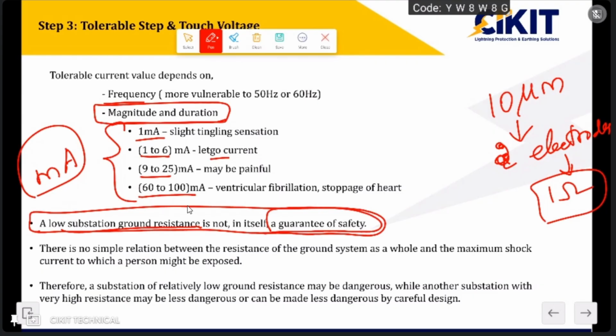They have also mentioned that there is no direct relationship between the safety and the ground resistance value. Even if the ground resistance value is higher, the design will be considered safe if the step and touch voltages are within the limit. So if I am designing a substation, the two important parameters to be considered are the step and touch voltages, and the ground resistance won't have much importance in ensuring the safety of your personnel.